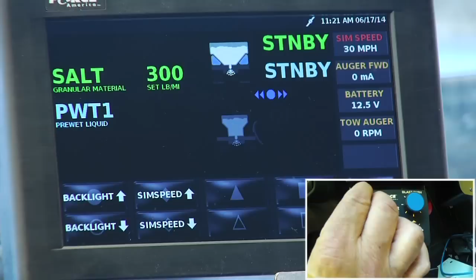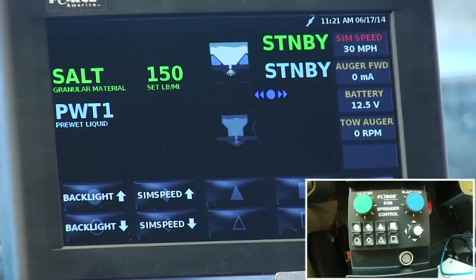Okay, and I'm going to set my rate for, let's say, 150 pounds. So what I would do now is I would start the truck up, and I would actually turn it on and run it for 2 minutes. I'd time myself for 2 minutes with a stopwatch, and I got my rate set at 150 pounds. So I would run it for 2 minutes. I would shut it off, and I'd go back here and weigh it. Well, if it weighed 155 or 149 or something, we're good. Okay, so we just proved that our verification test is accurate with our calibration.